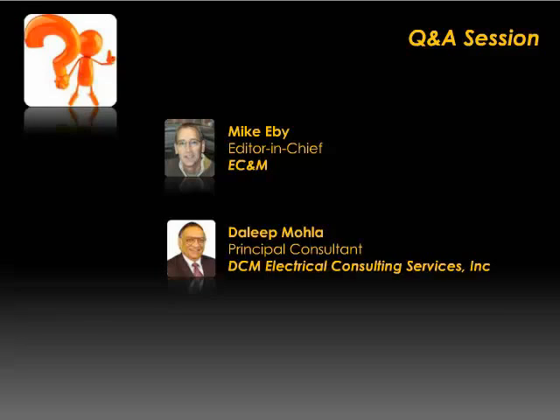Great suggestion. Okay, this has to do with a person that's dealing with a 480 volt delta ungrounded secondary. Says they have no ground fault detectors. How can we make this type of system safer? Okay. There is technology available to install a zigzag grounding transformer on the secondary and derive a ground detection system. So right now, technology is available. If you call one of those 4 names or 5 names we have shown you, they'll be glad to assist you. That is very common, because all 1950s and 60s installations were done delta-delta. You can derive an artificial neutral and have the same advantage as high-resistance grounding.